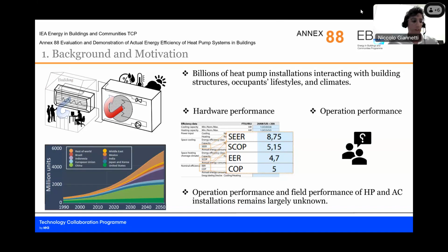The technology that we are targeting, as you have understood, is that of a heat pump, intended for both cooling and heating. So both heat pumps, hydronic or air-to-air or other types of heat pump such as ground source, and air-to-air, which also includes air conditioners. We know that this technology has been extensively installed worldwide. We can observe numbers that lead up to billions of units already installed worldwide in the case of air conditioners. These are operating systems that interact with building features, normally operate with inverter technology, so with a control that responds dynamically to given loads, and interact with variable lifestyle or comfort standards, but also with different climates worldwide.